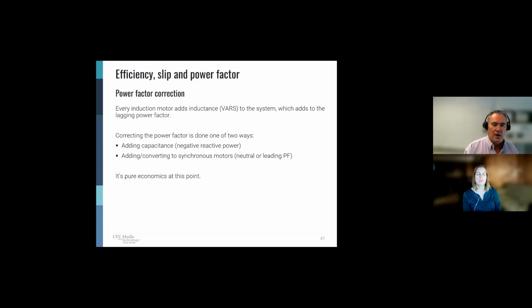We can do that one of two ways. We can add capacitance, which, as you'll recall, is the inverse of inductance, or negative reactive power. Or we can add or convert to a synchronous motor, which provides a neutral or leading power factor. It's pure economics at this point, okay? If you're responsible for operating the facility, you're going to want to do an economic analysis and say, it's going to cost me this much to do this, and this much to do that. It's not a technical decision really at this point.